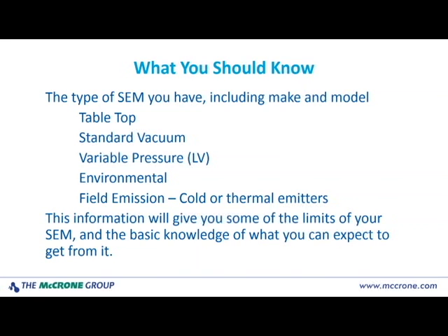You can put non-conductive samples into your SEM at variable pressure and you can dissipate the excess electrons that are building up in the sample. You also have what's called an environmental SEM. There's not a lot of these out there today — over all the years we've been teaching the course, never had anybody come take the course that actually had one. So they have very limited use. It's a slowly developing field with some very specific uses, but not a lot of demand. The latest SEMs and the ones that have the greatest resolutions are the field emission SEMs, now available in both cold or thermal emitters. So if you get this information together, it's going to tell you some of the limits and capabilities of your SEM and what you can actually expect to get from it.